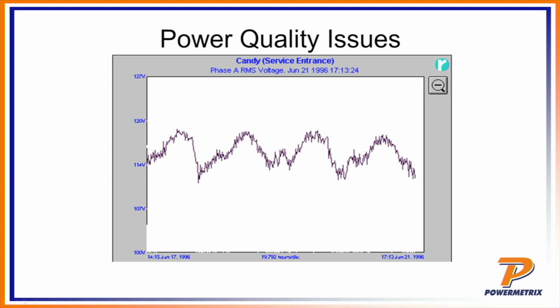Here's a picture of voltage variation over the course of a day. And so what you'll see is that if you come in early in the morning, this thing's typically riding up close to 120 volts. This is probably 8 a.m. when everybody comes into the building, everybody turns on the lights, turns on their computers, HVAC system kicks in. You'll notice that there's a large drop. And so that gradually sort of builds up over the course of the day and then just goes again. So you have a very cyclic phenomena. This particular system is only deviating between about 120 volts and 114 volts. So that's still well within the utilization range called out in the earlier slide. So that's probably not going to be a problem.